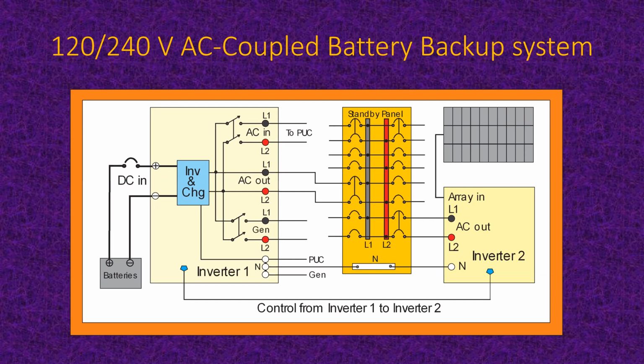And that comes in taking a look at this system carefully and noting that we started out with the sun shining and the utility up. So therefore, the solar can make electricity. It's inverted, turned into AC, goes to the standby panel. If the standby panel has all it needs from the solar, it sends it back into the AC out terminals, which sends it up to the AC in terminal and back to the point of utility connection, which may be the main distribution panel. The loads in the panel take what they want of it. Anything left over goes back to utility. That's your normal time. Your batteries stay charged as needed because when the power is up, either solar or the utility, the inverter is capable of charging the batteries.